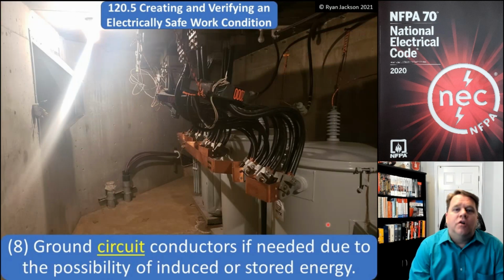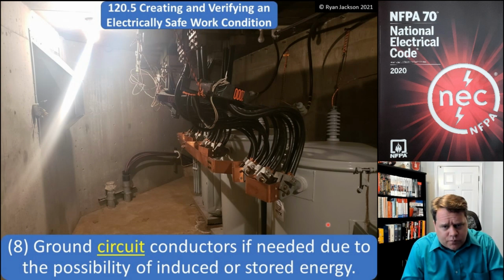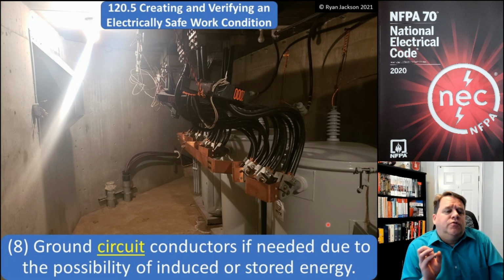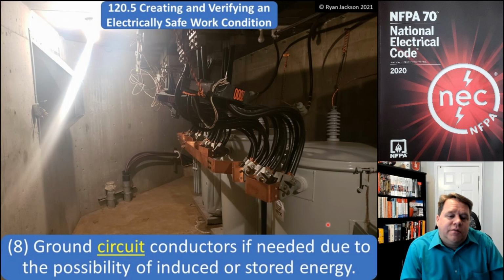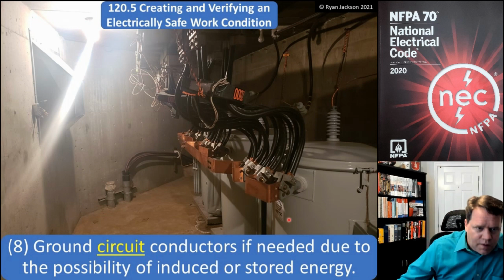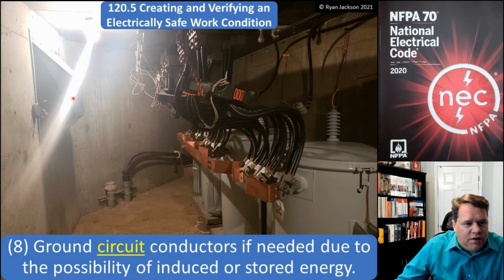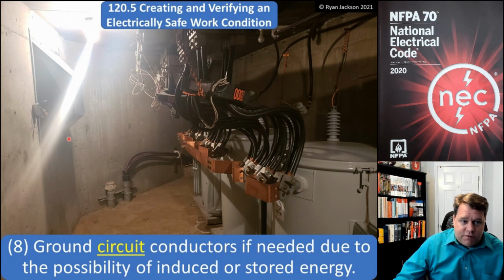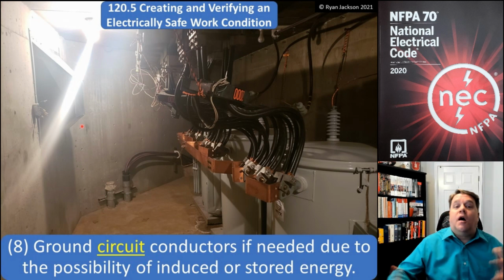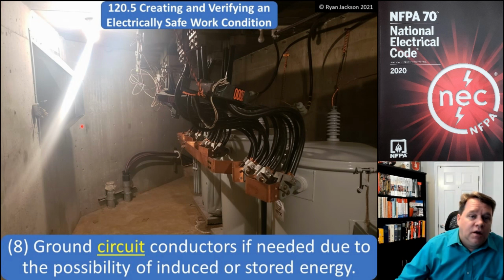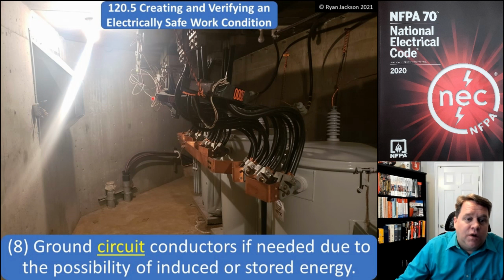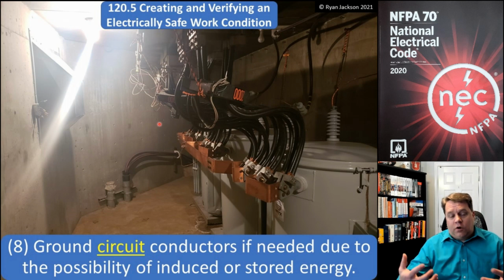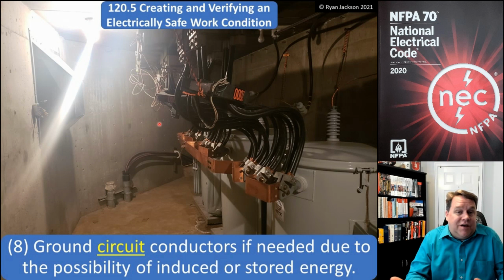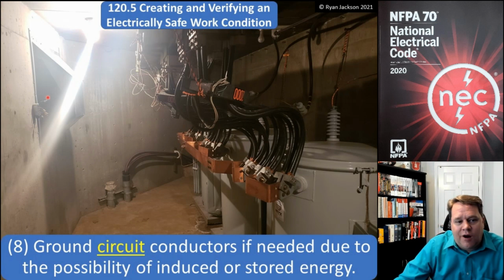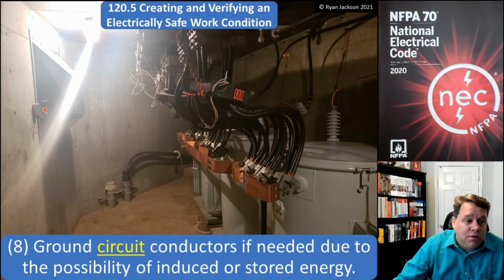The last thing that we have to do as part of creating and verifying the electrically safe work condition, and this doesn't come up too terribly often, is to ground the circuit conductors if needed due to the possibility of induced or stored energy. All right, so I'm working on this light switch over here on the left. Now, I've gone through all the steps. I've shut everything off. First thing I did, of course, is I verified all possible sources and interrupted the load, went through the whole thing, locked it out, verified that it's not on. But this is also a couple of feet away from a 25,000 volt transformer. Transformers work by inducing voltage. That's how they work. Could it possibly induce voltage on these conductors over here? Sure. Yeah, that could happen.